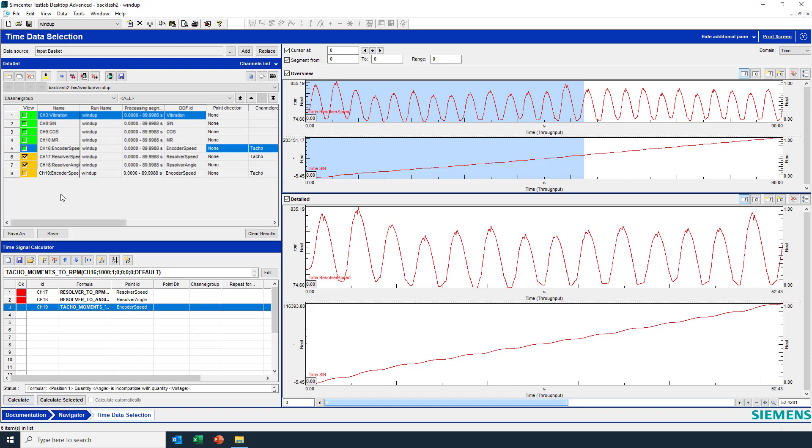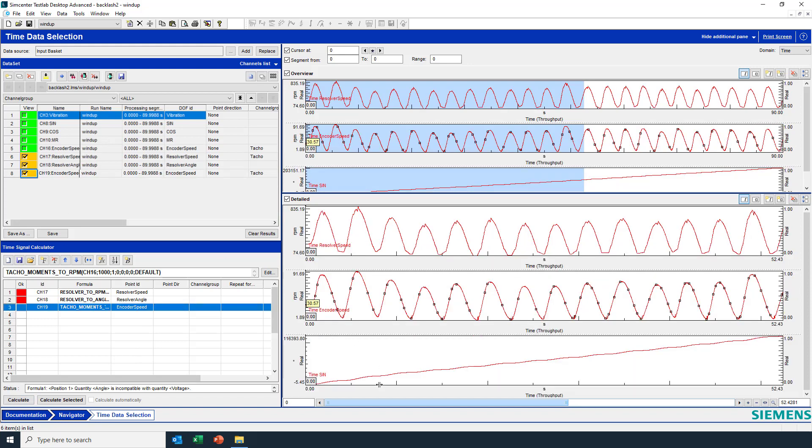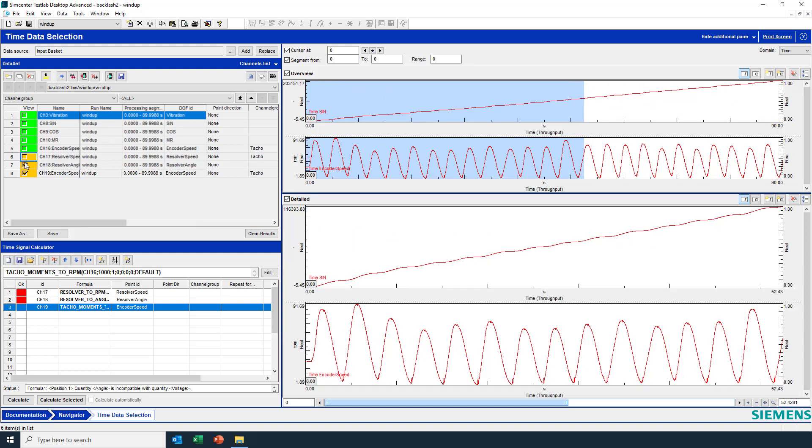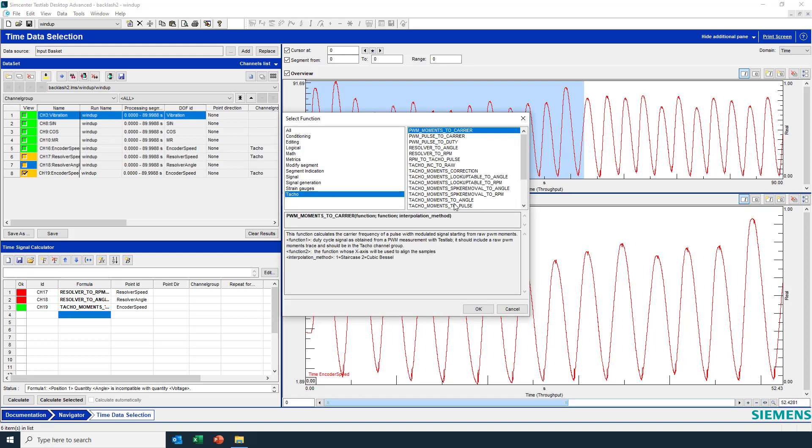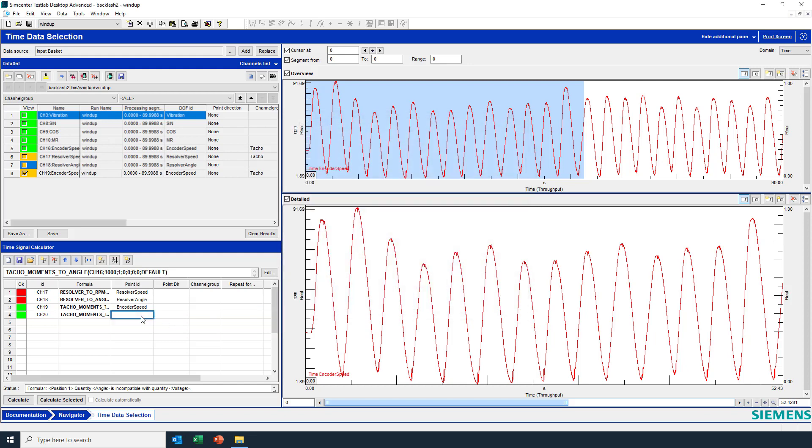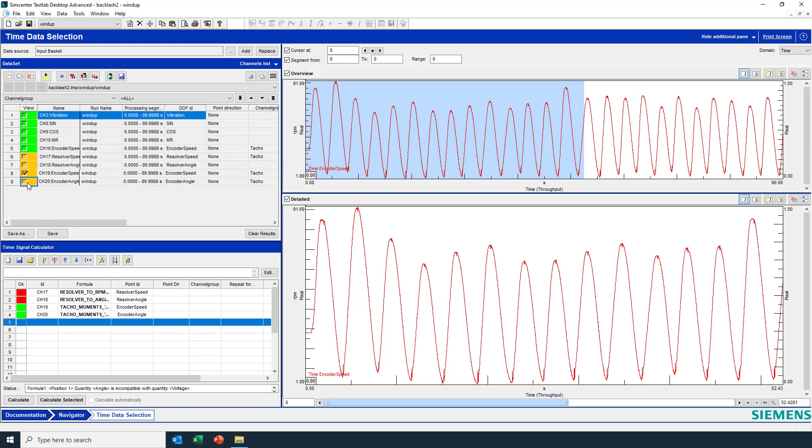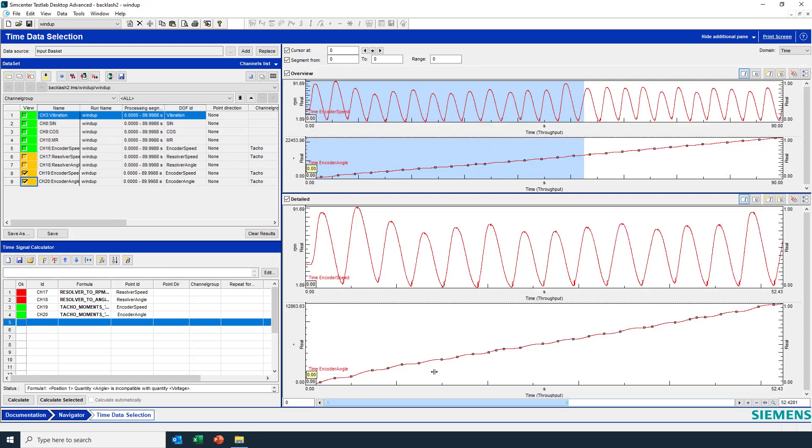I'll hit calculate. Take a look at this. Turn off these. And yes the rpm looks like I was expecting. About goes up to about 91 rpm. So I can do the same thing, but now I will do tacho moments to angle, calculate the angular displacement, also on channel 16. Thousand pulses per rev. And this will be the encoder angle. Calculate. And there we have an ever increasing angular position.